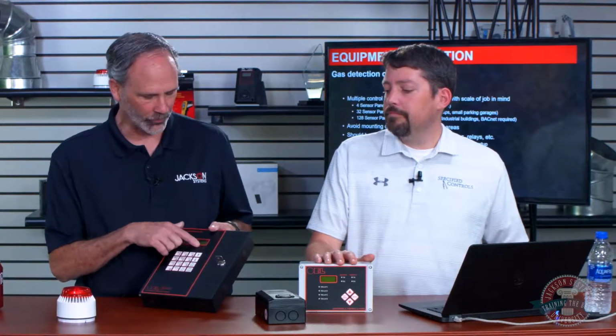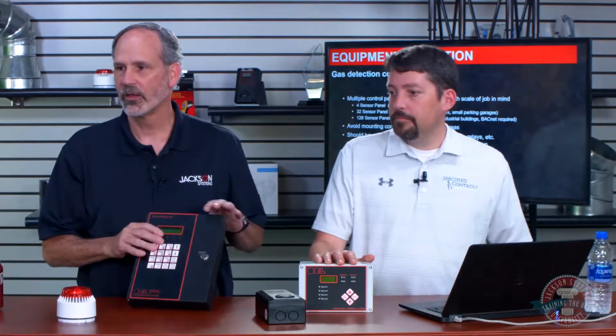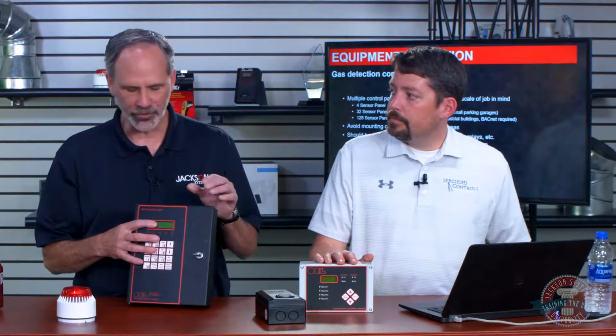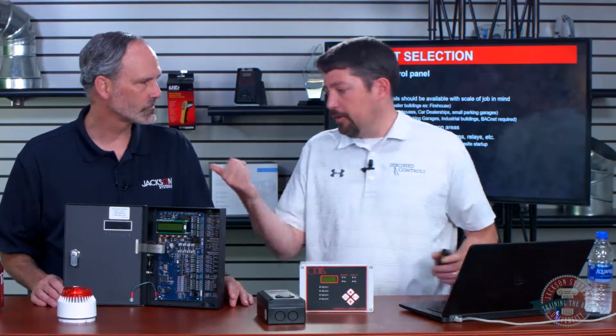On the sensors, if one fails, does that turn that light on? Good question. Depends. The answer is, if we set it, either one. The control panel tells you there's a failure. If it's put in a closet, you have to have somebody open that door regularly. You're right. So it turns on a little failure light here. The screen tells you which sensor failed. The question was, if we have a sensor failure, how do we know? It turns on a failure light, it tells you which sensor failed, and there's an output specifically designed for your strobe and horn. If you tell it to turn that on for a failure, it does. You don't have to do that, but it's just a checkbox.